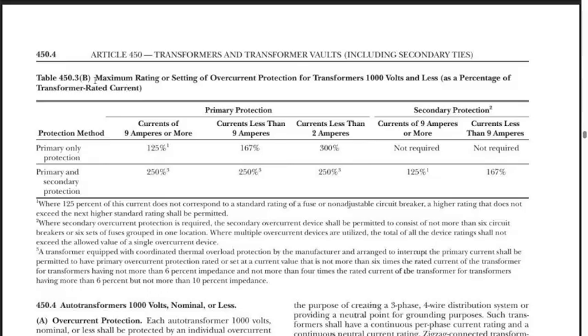Then this is what it says for maximum. The largest size rating is what that means, maximum breaker. All right, the biggest breaker or setting that I'm going to use to protect a transformer shall follow one of the bottom ones down here.